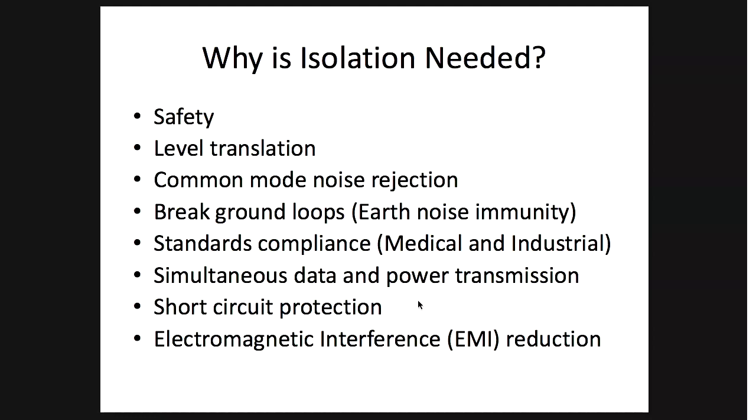So that is the reason, non-examinable, but I want to make sure that this is the isolation technique. All the medical devices have multiple safety features, and they will be using isolation techniques. Mainly you want to isolate from the AC. In medical devices, you will see they use a lot of things to isolate whatever sensor you are connecting from the main power supply. A lot of isolation techniques.